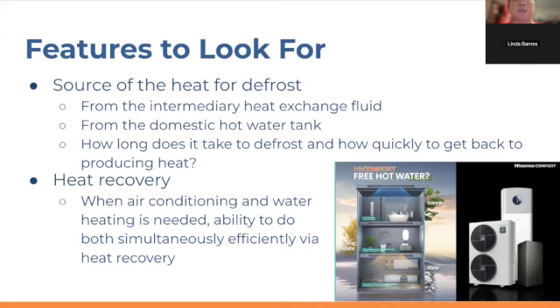And well, it depends on your hot water habits. It's true that in the summertime, your cooling load is really big, and the amount of energy you'd actually need for heating the kind of warm city water coming into the home is not that high compared to the amount of air conditioning load. So the number of hours out of the year when you're actually doing heat recovery is maybe kind of small. But if you take a daydreaming shower, or you sit in your bathtub and fill it all the way up, then if you have high hot water or warm water usage, then yeah, the heat recovery would be beneficial. So how useful heat recovery is really depends on your hot water usage habits.